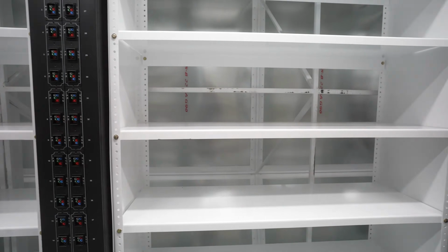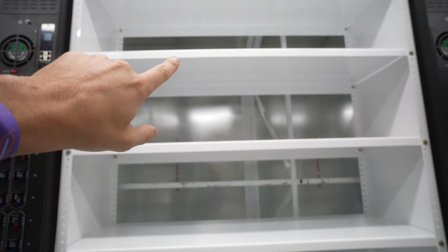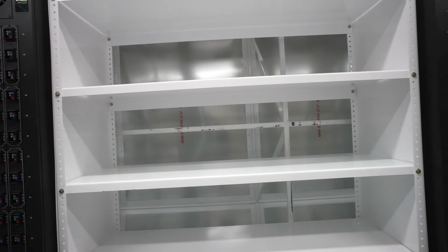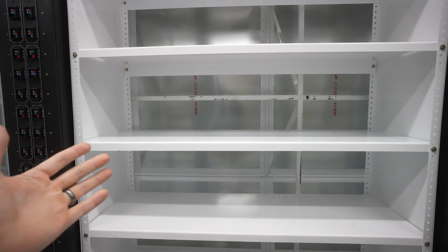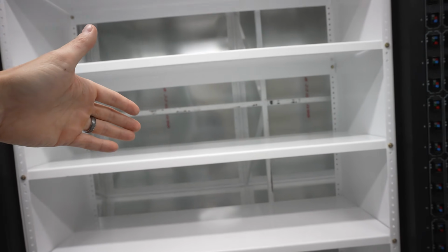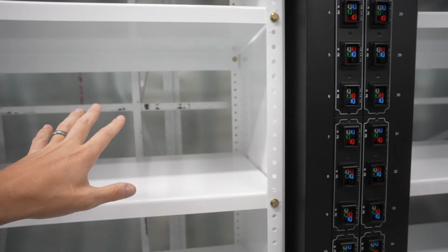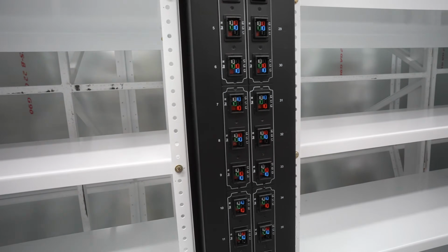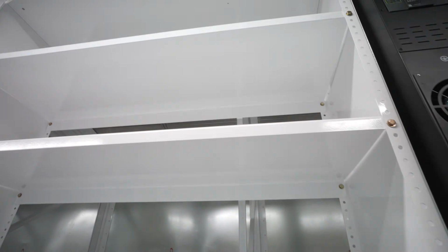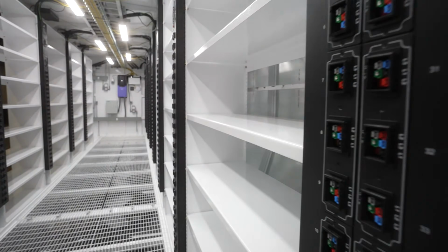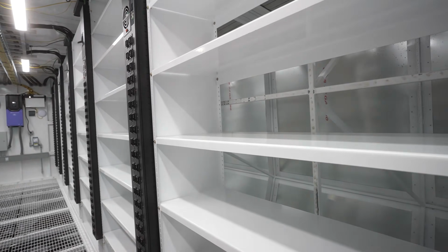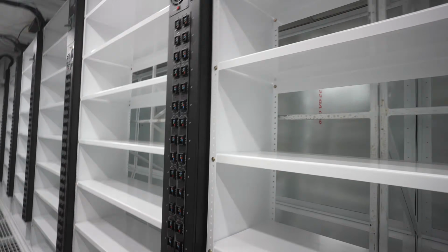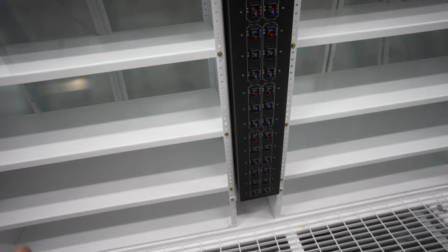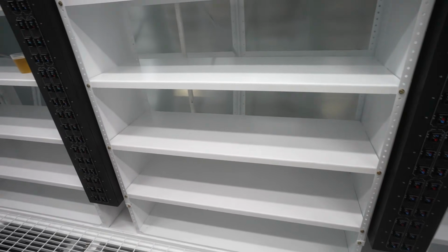And you might actually want to see one in person, because is it built out properly where when the miners are blowing out, do they have any significant backflow because of not enough volume coming out, since it has to blow out at a certain rate. And the louvers on top need to open up for these miners and actually be able to have all that airflow come out. Because again, this is not a megawatt, you got to keep that in mind. This is like 5 megs.